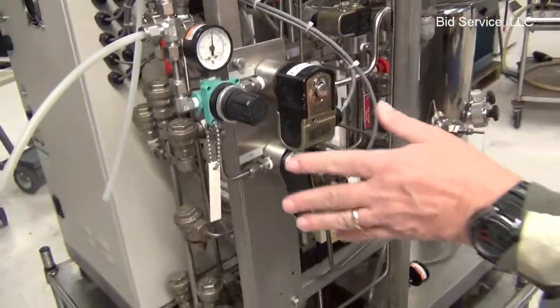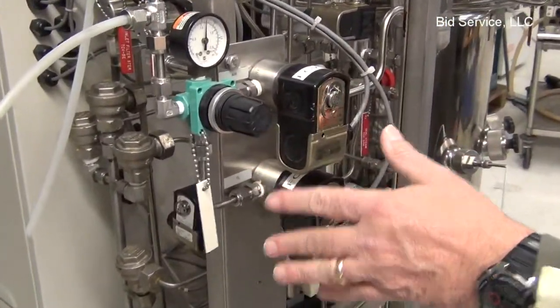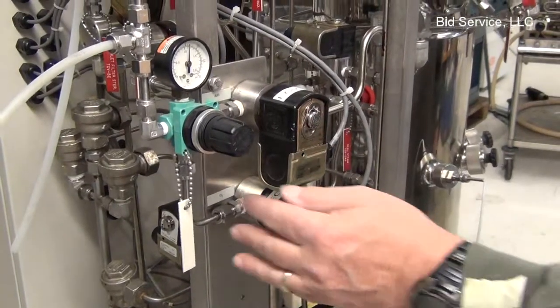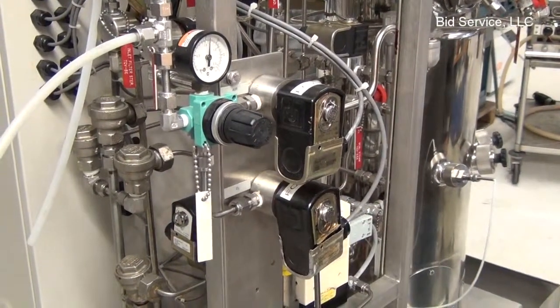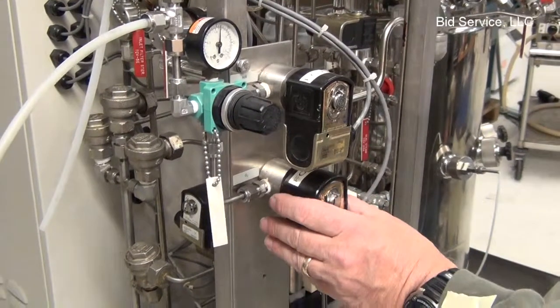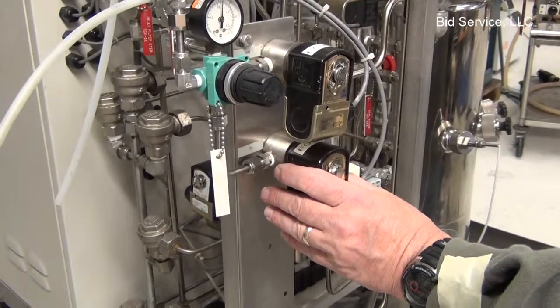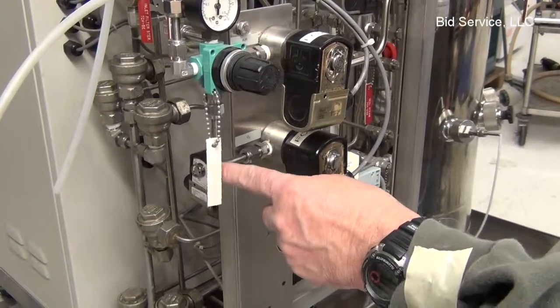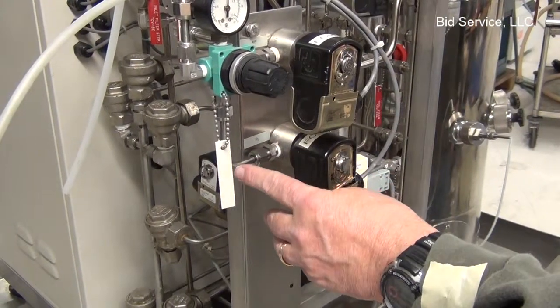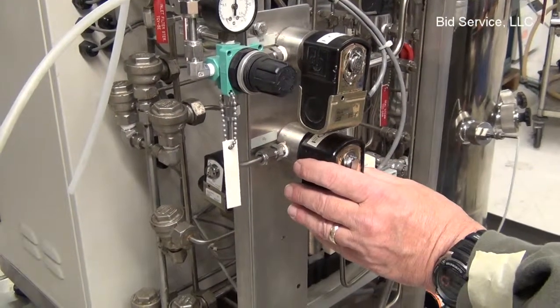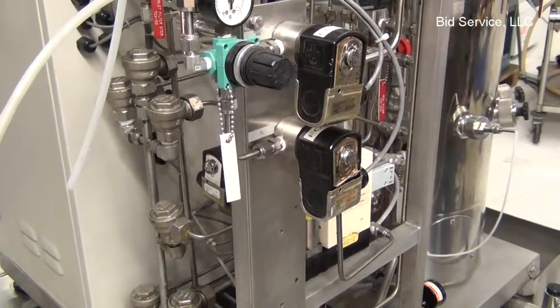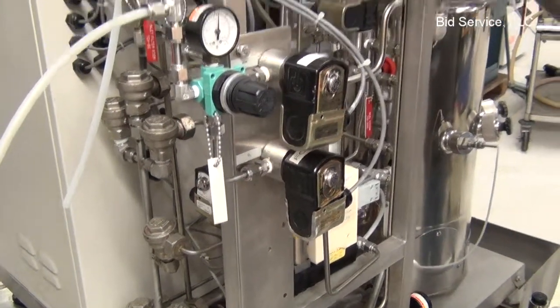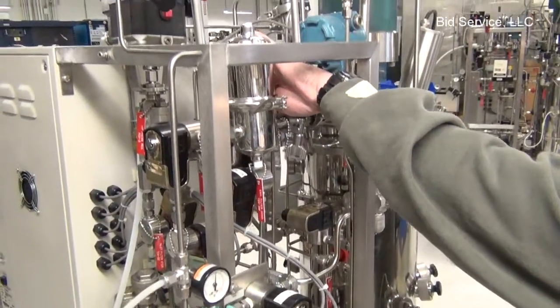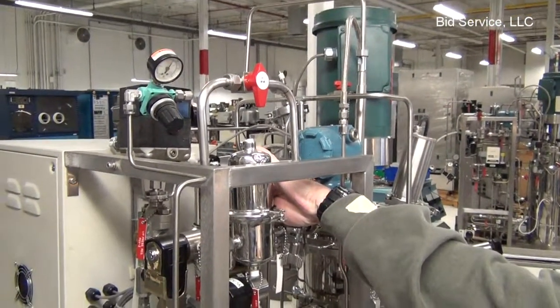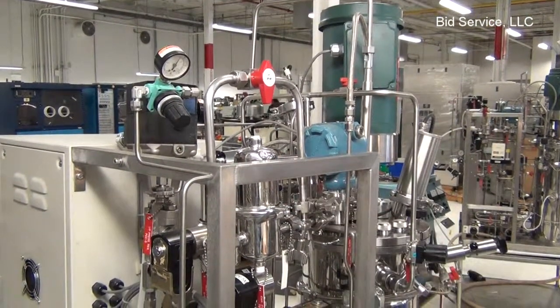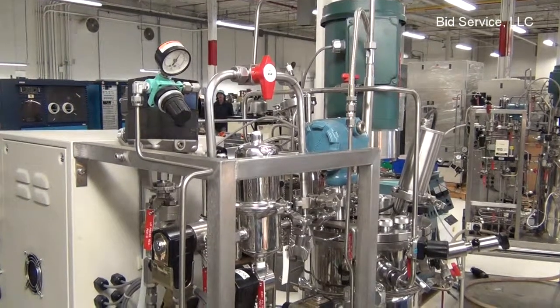On the other instrument, this is where your dissolved oxygen was, a separate port. On this one, it was not designed that way. What I did do, however, is add another solenoid on this machine so that if you did decide to go with a separate dissolved oxygen input, the solenoid would be available to you. Up here, your filter elements, again, are clean and functional, and you shouldn't have any difficulties with them.